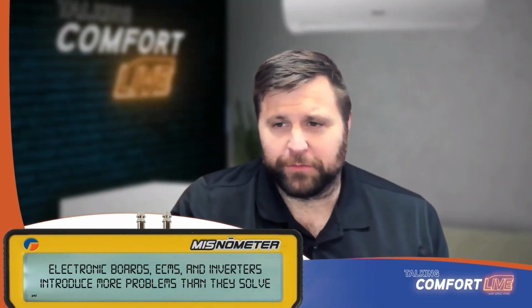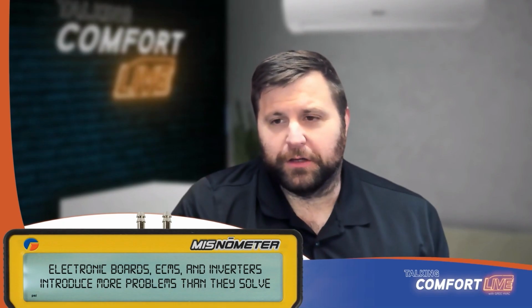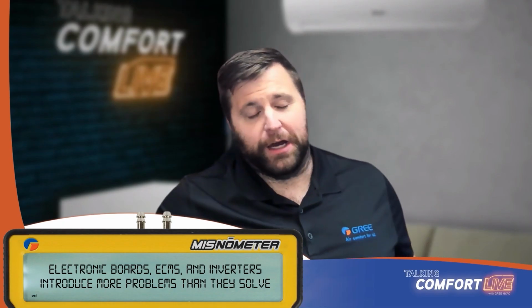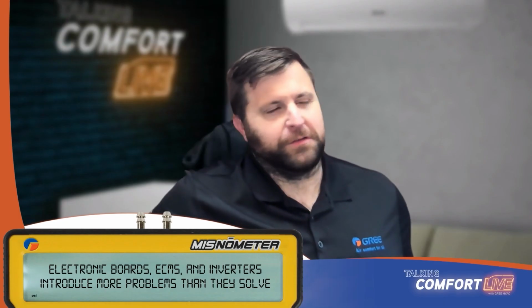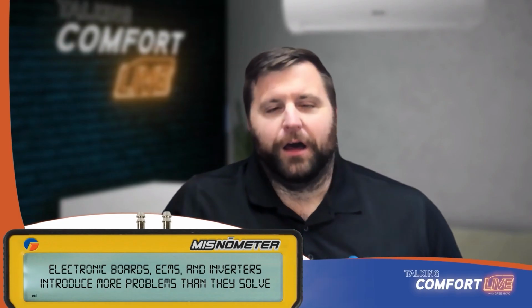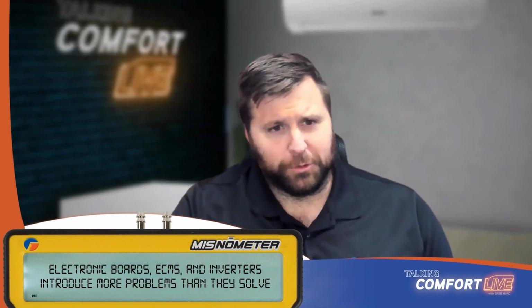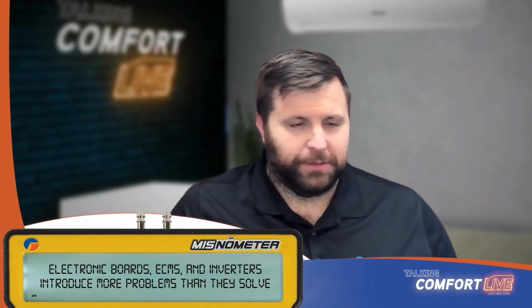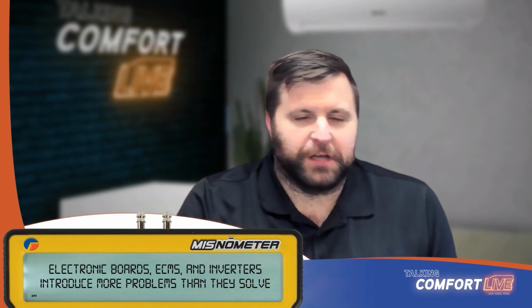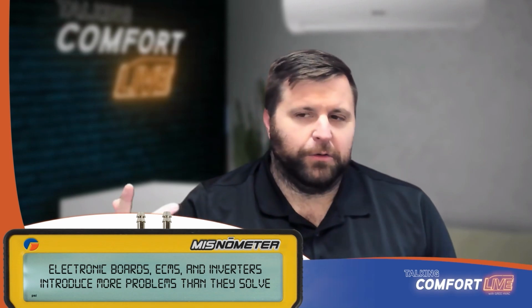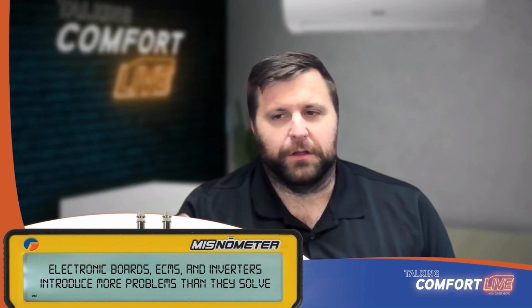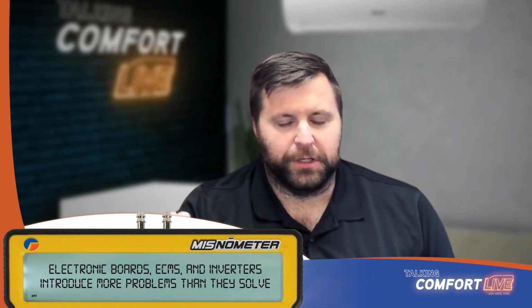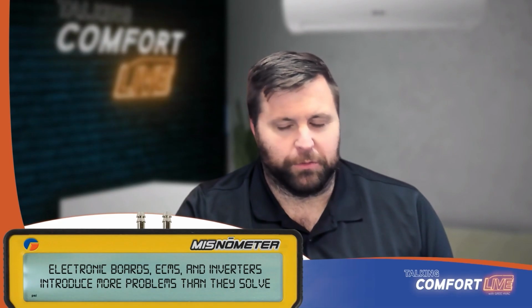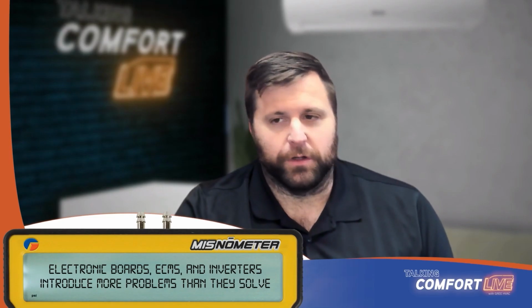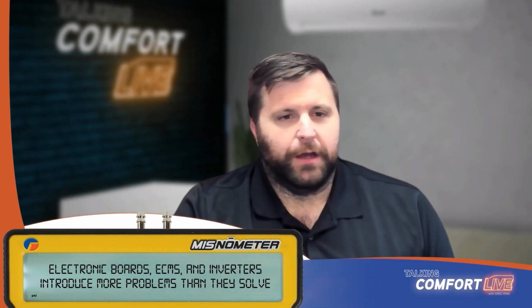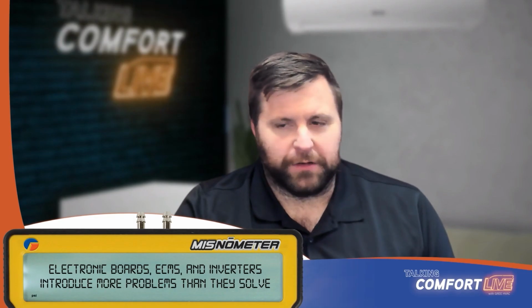I think you make a good point as far as being able to protect itself. I know we've seen quite a few times, you and I especially, systems that didn't have, let's say, a low pressure switch. Whatever SEER equipment that was at the time didn't have one. The filter gets clogged or the coil gets dirty, and you've got no way to monitor whether liquid's coming back, or in the case of a low pressure switch, that it's out of refrigerant. Nothing would cause it to trip, nothing would actually shut down the system.